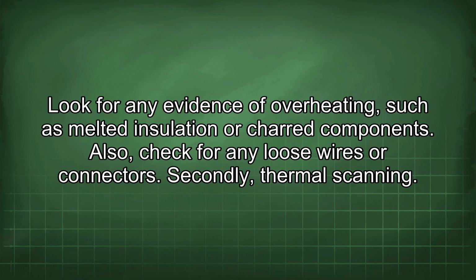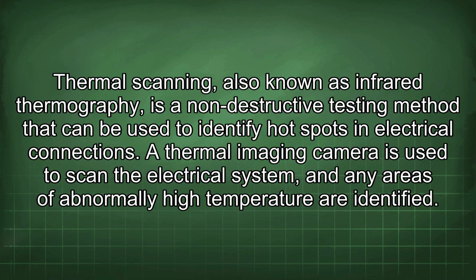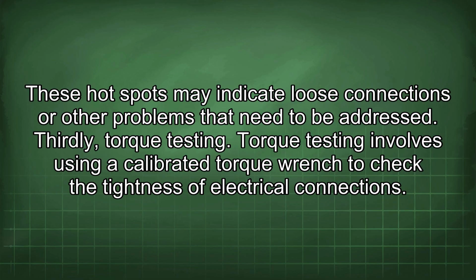Secondly, thermal scanning. Thermal scanning, also known as infrared thermography, is a non-destructive testing method that can be used to identify hotspots in electrical connections. A thermal imaging camera is used to scan the electrical system, and any areas of abnormally high temperature are identified. These hotspots may indicate loose connections or other problems that need to be addressed.